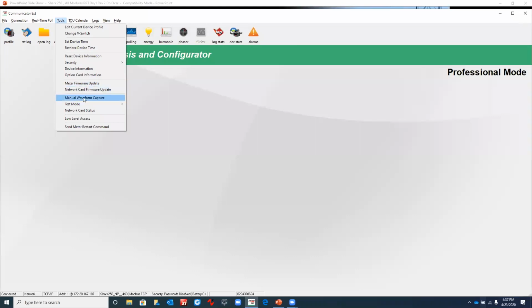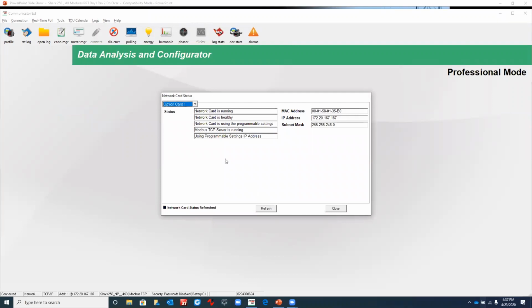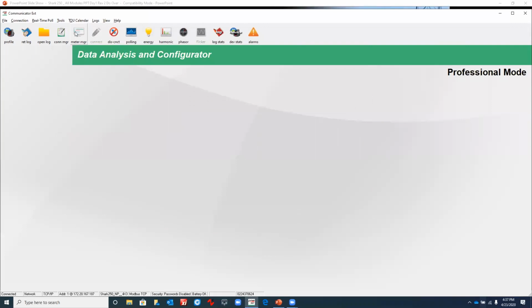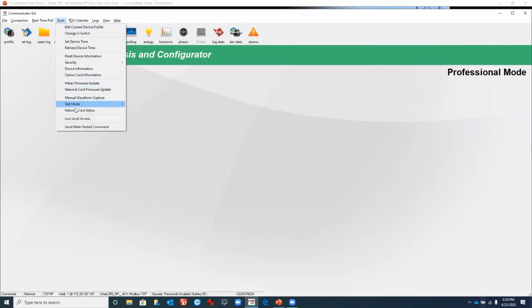Then there's the manual waveform capture test mode. If you want to test the meter, utilities normally would use this function, and you want to do presets, which is a nice feature. You can test the meter, put it in test mode after you finish calibrating and testing the meter. You want to adjust the registers as if the meter was never removed from service. The network card status shows you some status information that everything is working properly. The MAC address and so on is also provided here. So basically, the tools allow you to do a lot of the fine tuning when setting up your meter, and additional external testing and so on, as we mentioned.